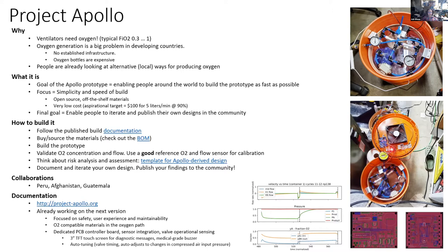The goal of the prototype is to enable people around the world to build their own prototypes as fast as possible. We focus on simplicity and speed of builds — as soon as you get the materials in the mail, you should be able to build this oxygen concentrator in an afternoon. The cost is very low. In bulk, we aspire to a $100 oxygen concentrator delivering five liters per minute at 90% oxygen concentration.